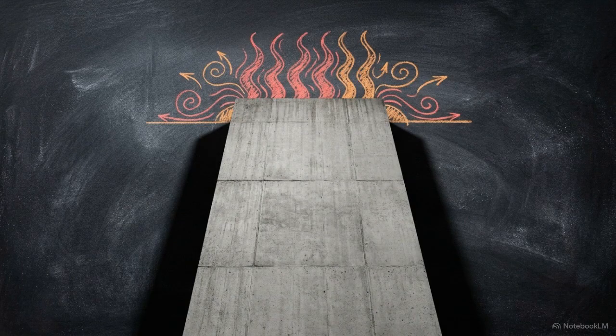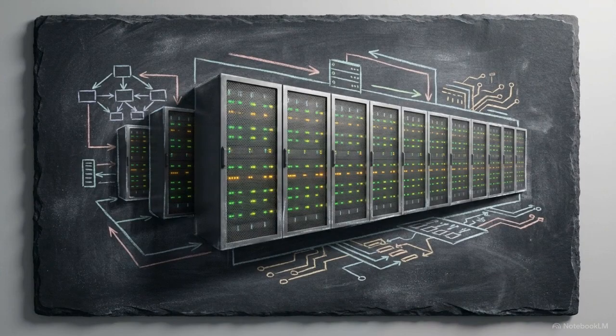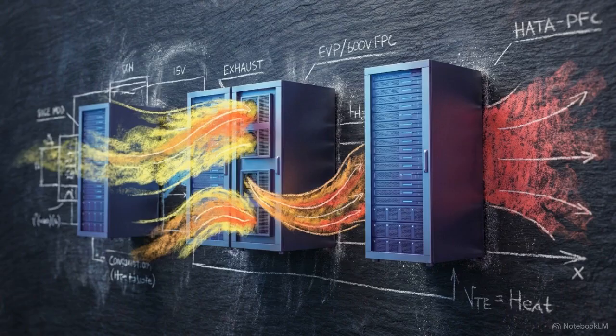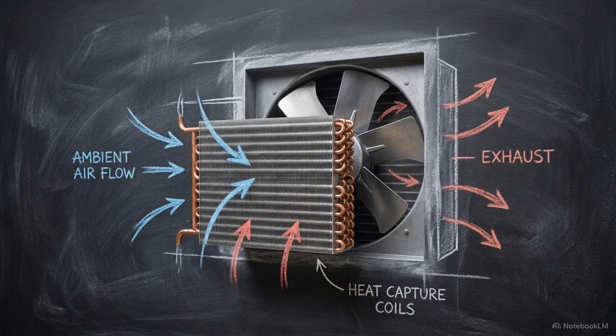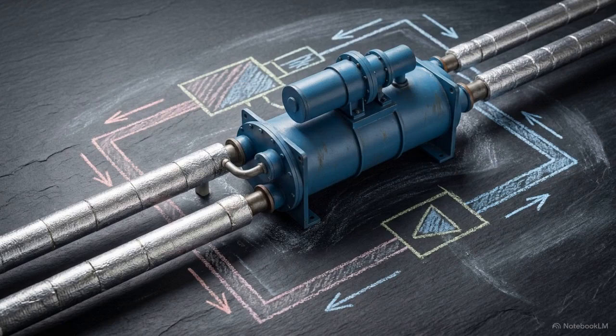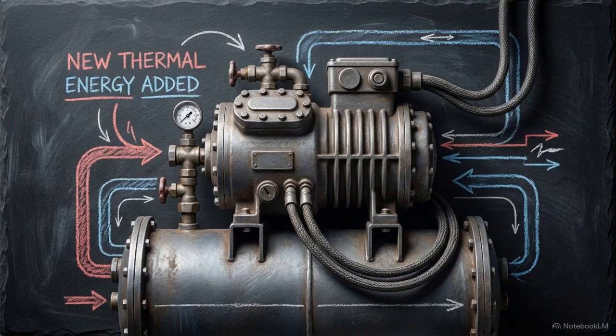Now that heat must be physically evacuated to the atmosphere. Beyond the liquid captured load, we must account for the remaining 20% of IT heat. This 28.8 megawatt load escapes into the data hall as ambient heat from memory, storage, and networking equipment. Computer room air handlers pull this ambient heat across cooling coils, trapping the energy inside a separate chilled water loop that feeds the mechanical chiller plant. The mechanical compressors required to run those chillers inherently add 4.1 megawatts of new thermal energy to the system.